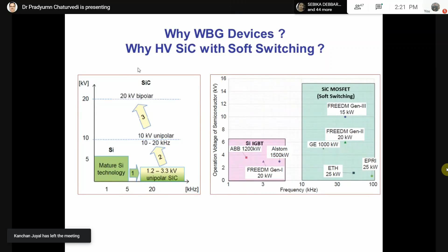Now around 20 kV bipolar silicon carbide devices are available, which can work at around 10 to 15 kilohertz. And if you try to reduce the kilowatt rating, you have to go up to several hundreds of kilohertz of switching frequency, because SiC and GaN devices have very low on-state resistance and very low turn-on and turn-off losses. So switching losses are much reduced.